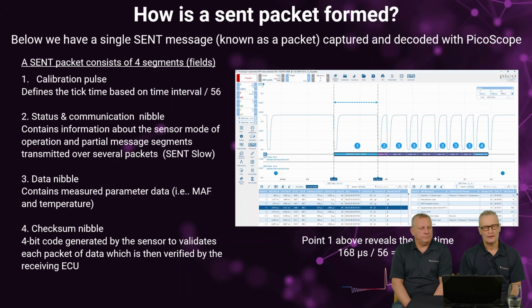Now the data nibble contains exactly that - the measured parameter data. So whatever it was predominantly designed to deliver, so mass airflow, temperature, pressure. And finally the checksum - a 4-bit code generated by the sensor to validate each packet of data, which is then verified by the receiving ECU. So checksum is common to these protocols that we've discussed through this series of videos. One form or another, there is a way of validating the packet sent and the packet received.